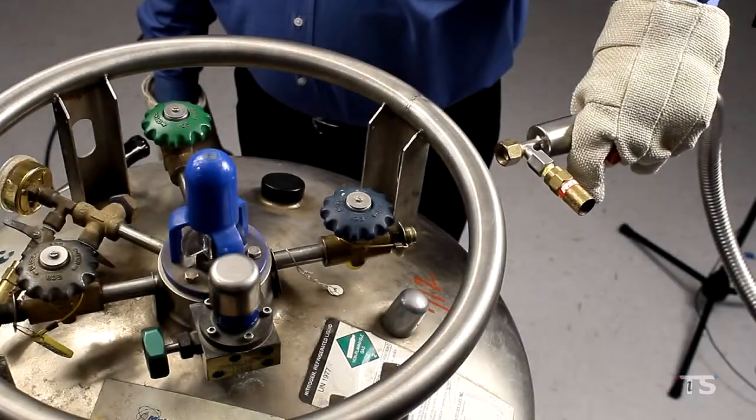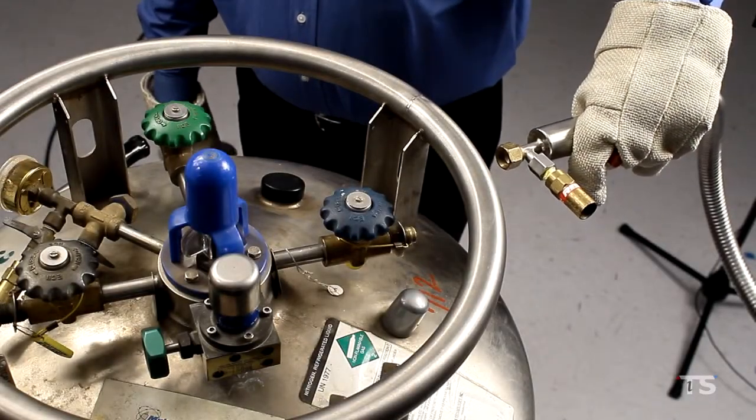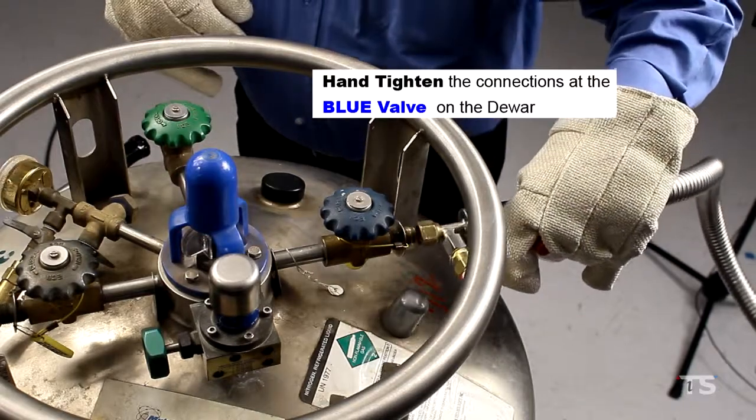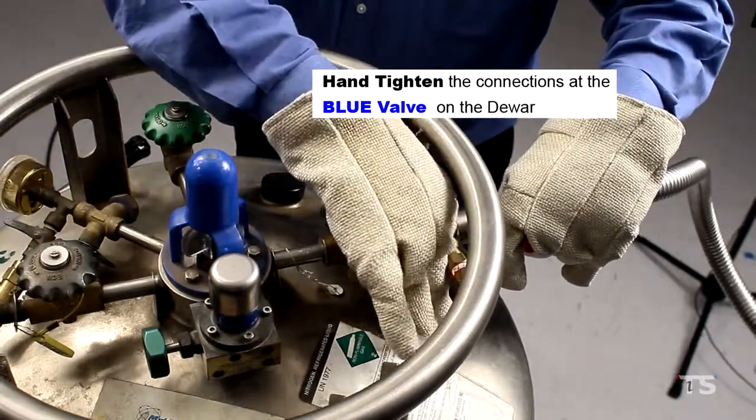We will start by hand tightening your coolant lines at the Dewar and chamber. First, hand tighten the connections at the blue liquid valve on your Dewar.